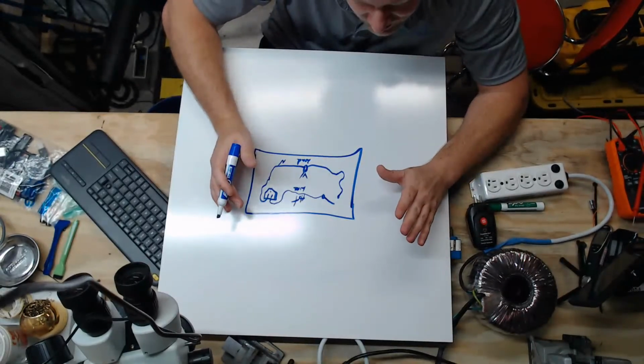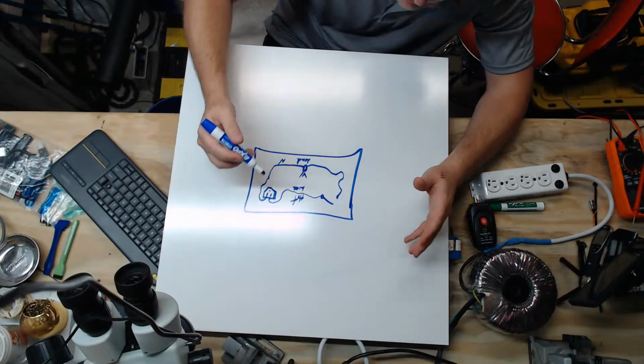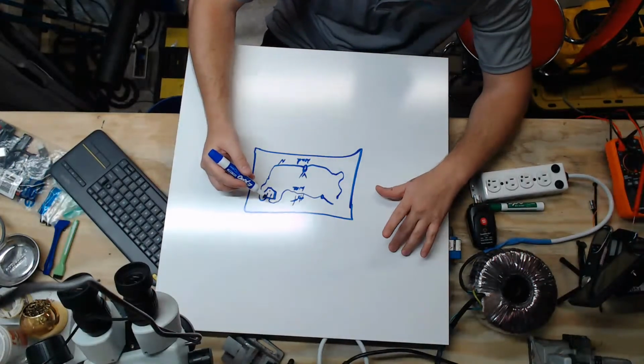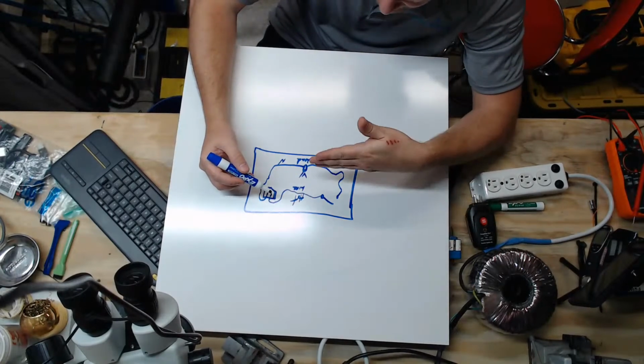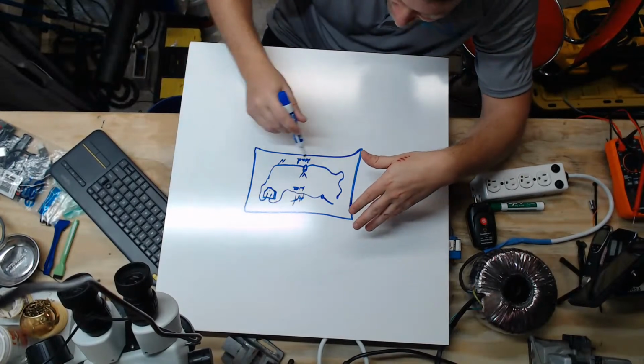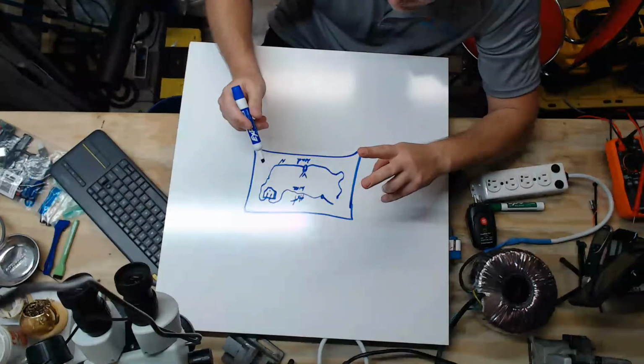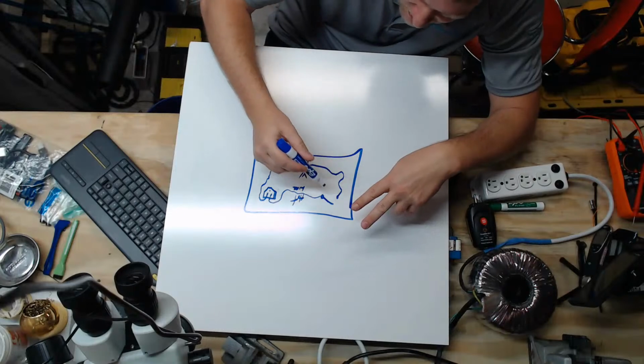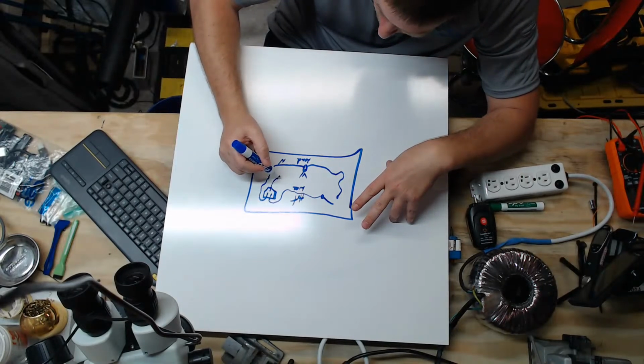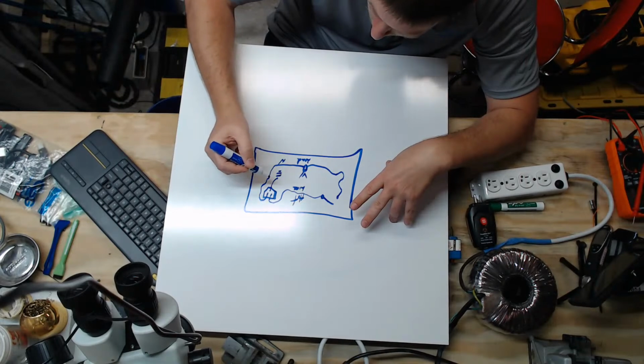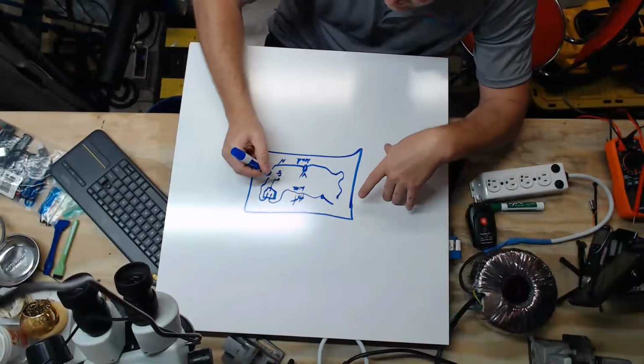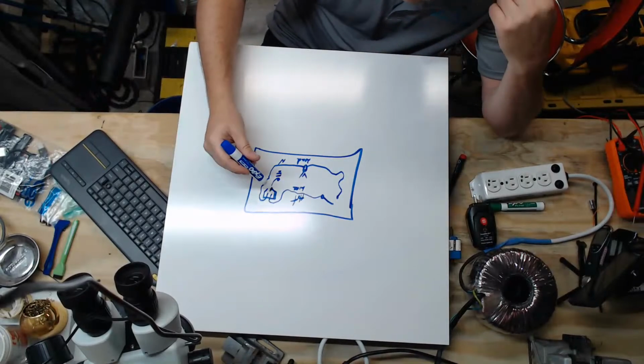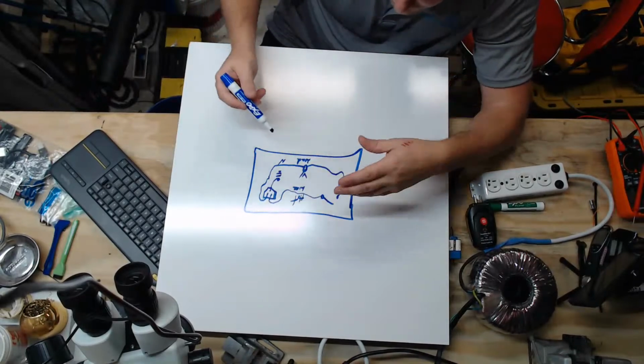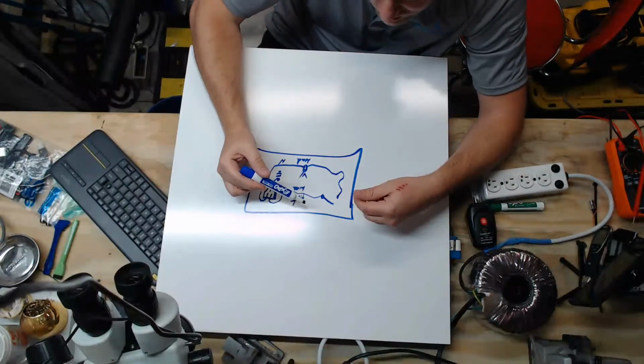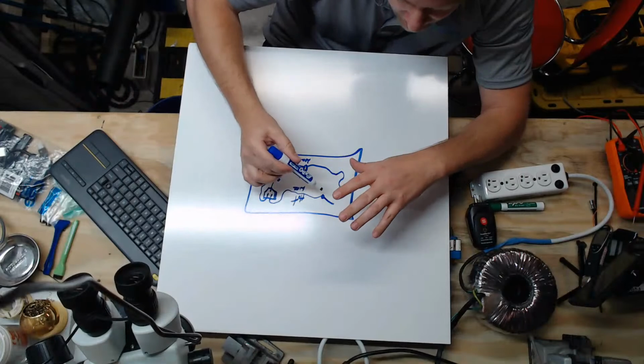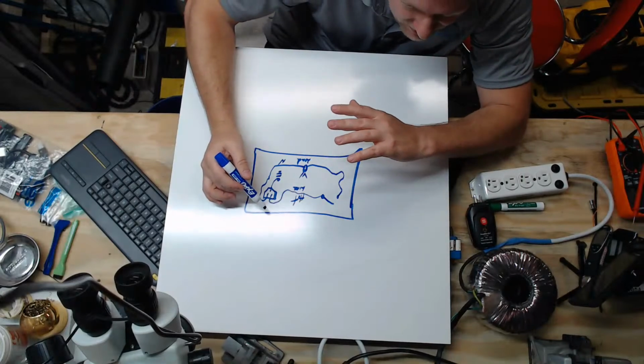Okay, so guys, this is the problem. The reason polarity is so important in medical equipment is because of your switch side and your line side, your neutral side. If you take a look at this, your whole device is going to be wired with ground to here. You have a lug inside your device that's going to be grounded. You're going to have neutral, which is going to go all the way through the device up until the power switch. And then hot is going to be the shortest. It's going to be the shortest power cable in your entire device.